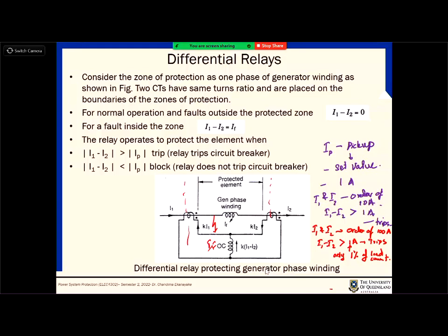Now, an extension of these differential relay schemes is called pilot relays. When you have transmission lines, you can put a differential protection scheme at the beginning of the transmission line and at the end of the transmission line, and then you can see whether there is any sort of fault in the transmission line. Then there will be a current difference, because the transmission line can be defined as one unit.